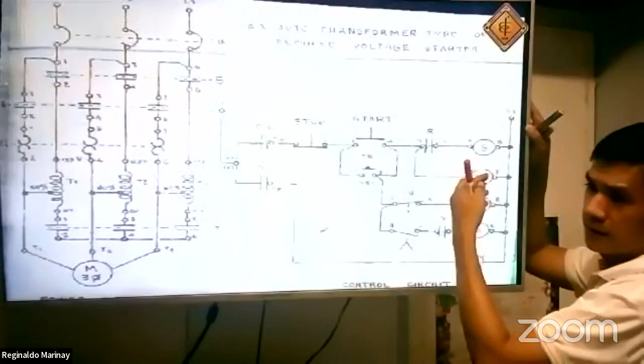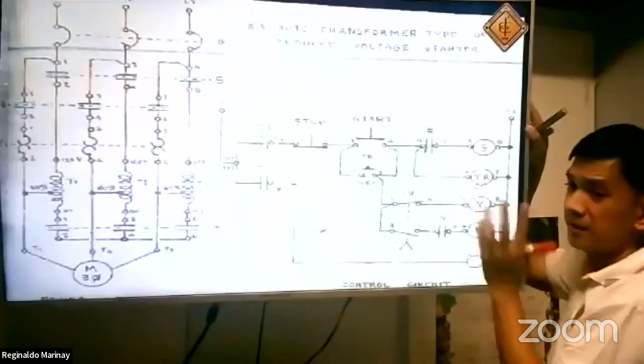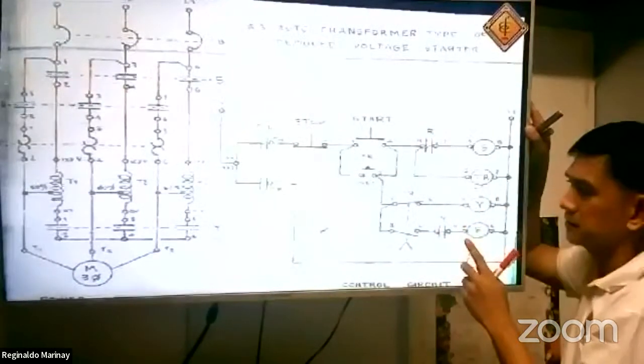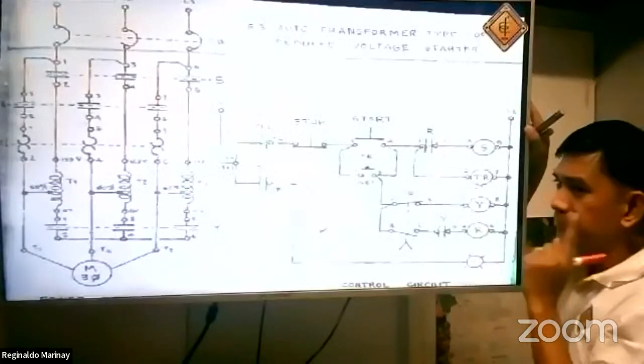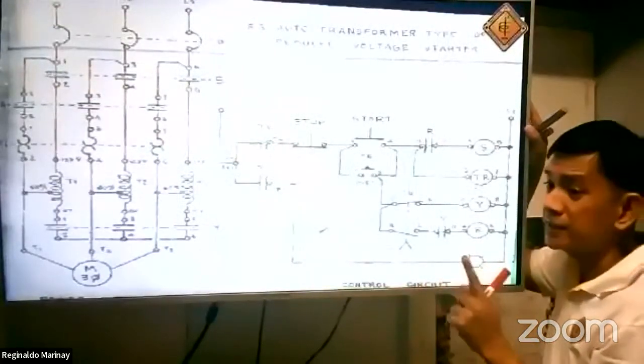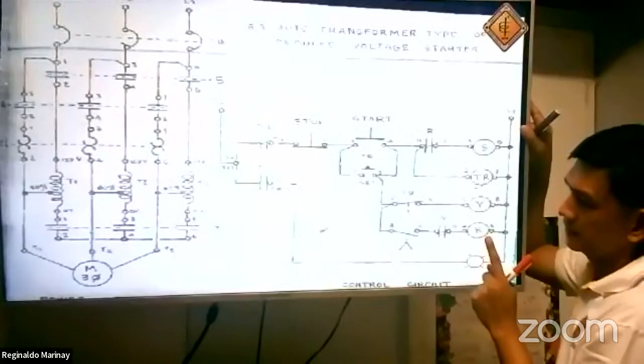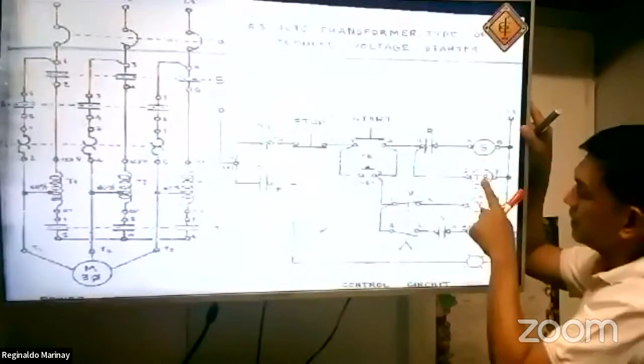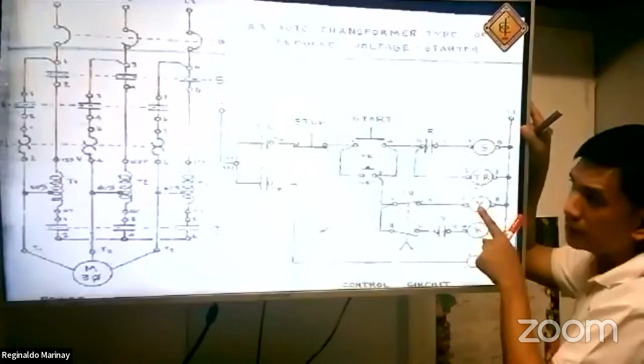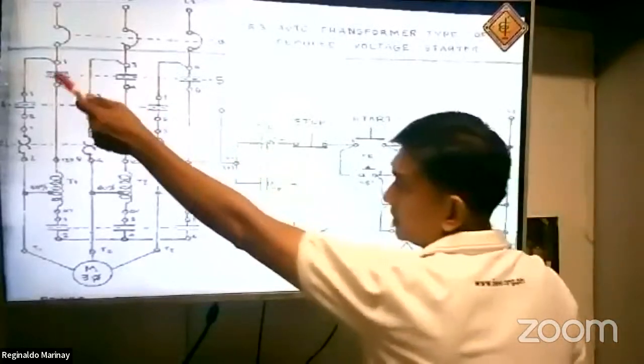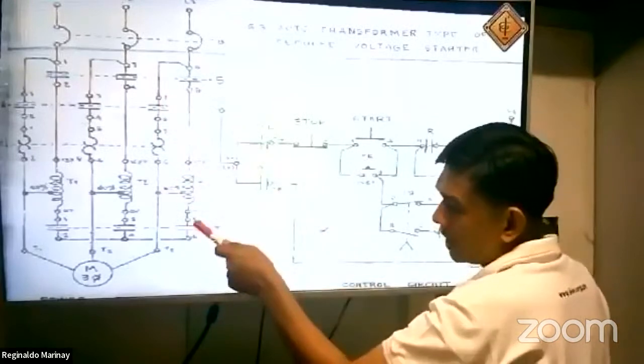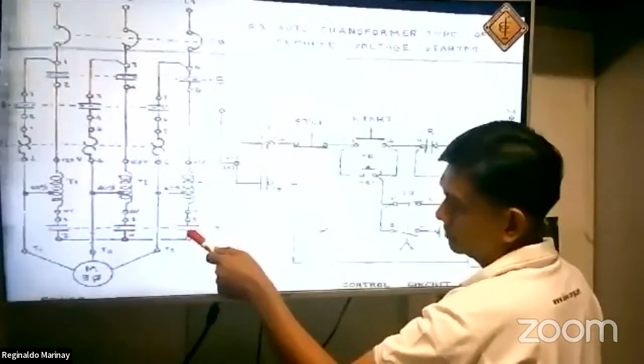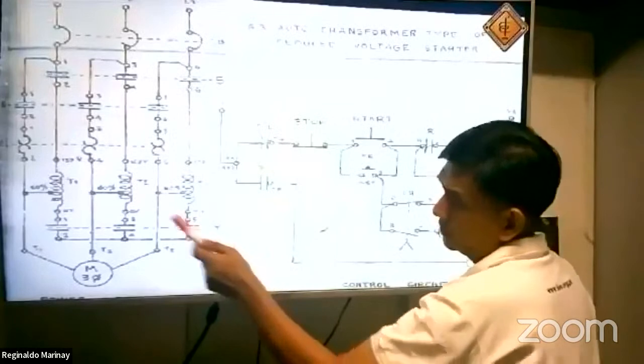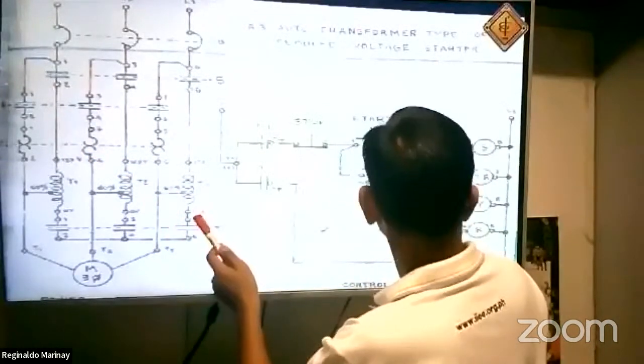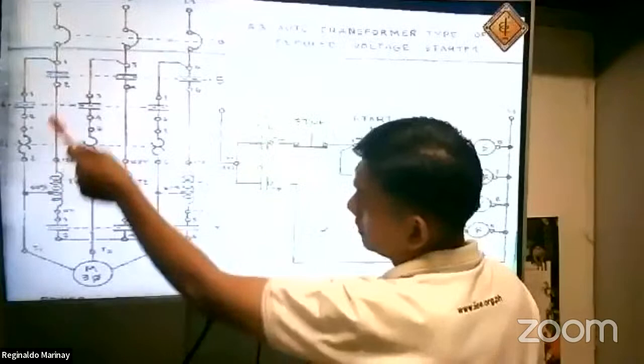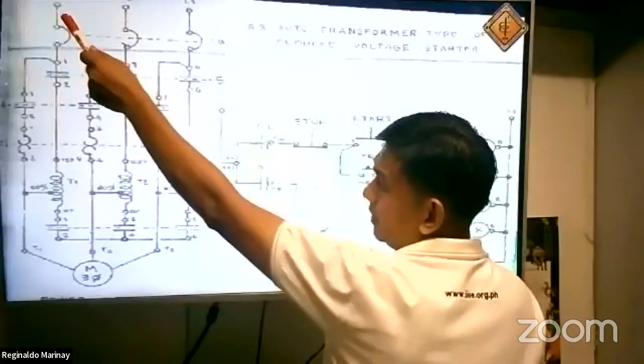Okay. Let's say 3 second setting. What will happen from 0 seconds to 2.99 seconds? Remember, the timing relay and the Y contactor are energized. The S is energized, so this will become closed. The Y is energized, so that will become closed. Where does the current flow? The current flows in this direction. Take a look here. This is energized, the S. The current will flow here.